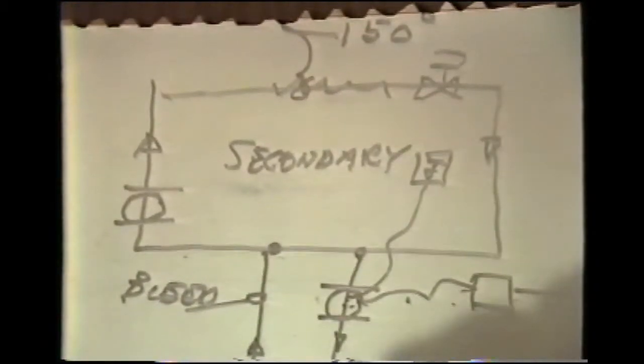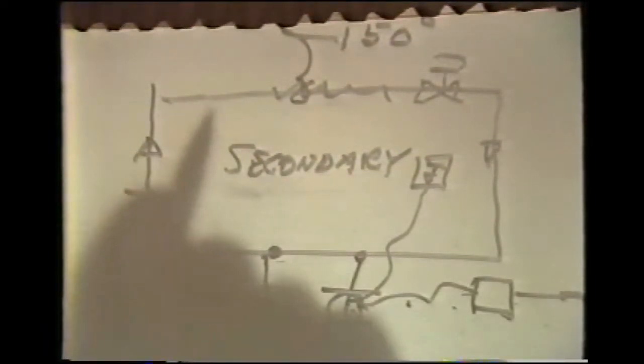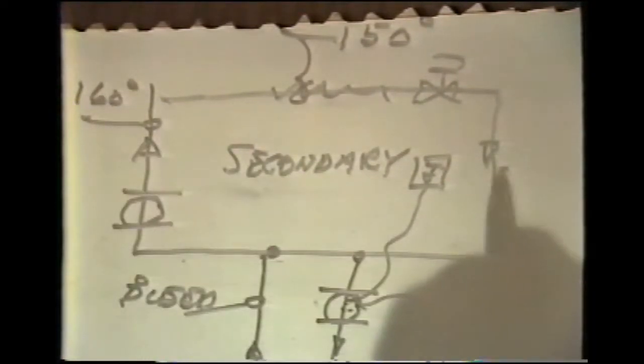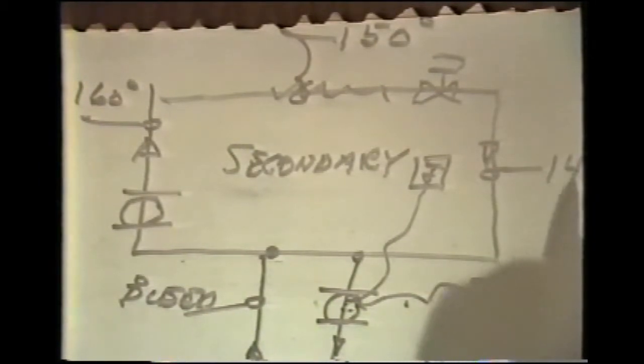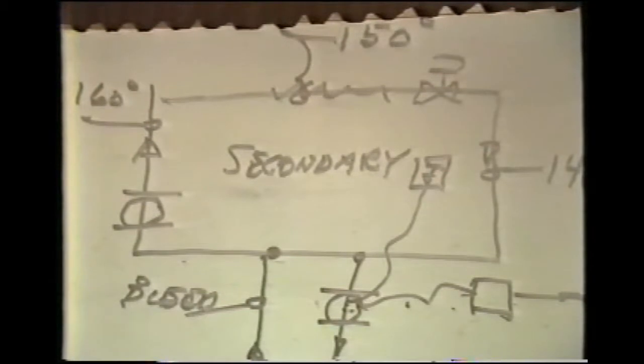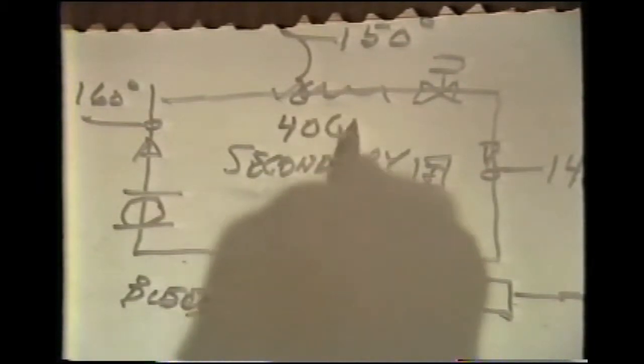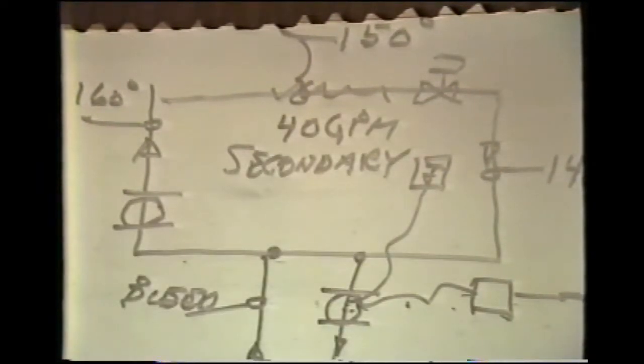Supposing in that secondary circuit we had a water temperature need of, as a mean water temperature of 150 degrees. And we're going to circulate this at a 20-degree temperature drop. This would establish then that we would have 160 degrees as supply water temperature, 140 degrees as return water temperature, and we would establish a flow rate need of 40 GPM based on the load of 400,000 BTU.